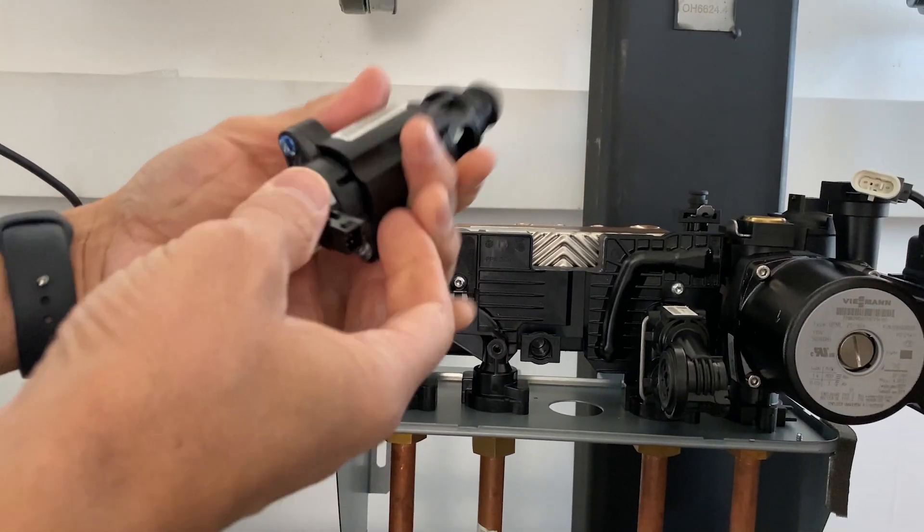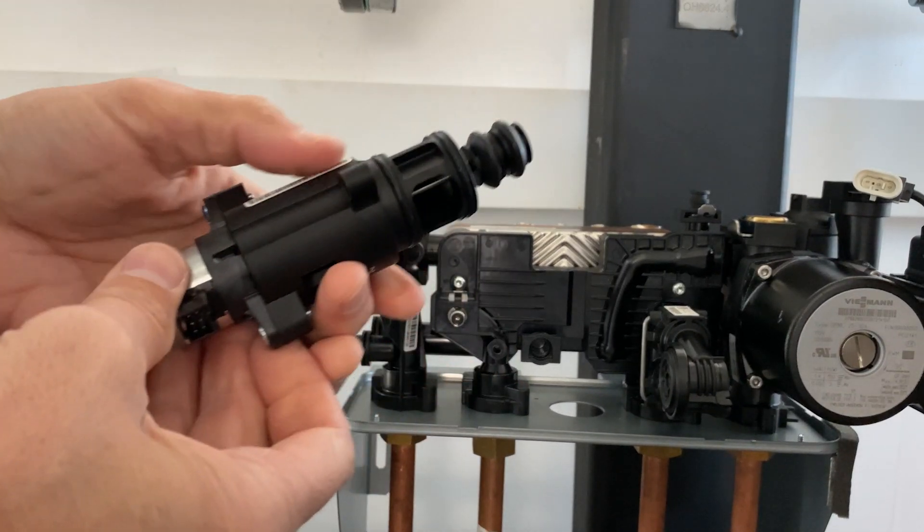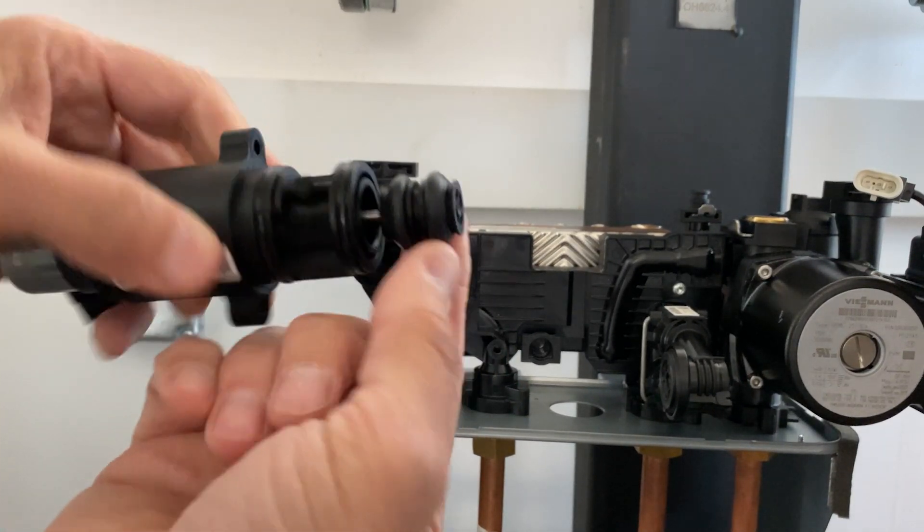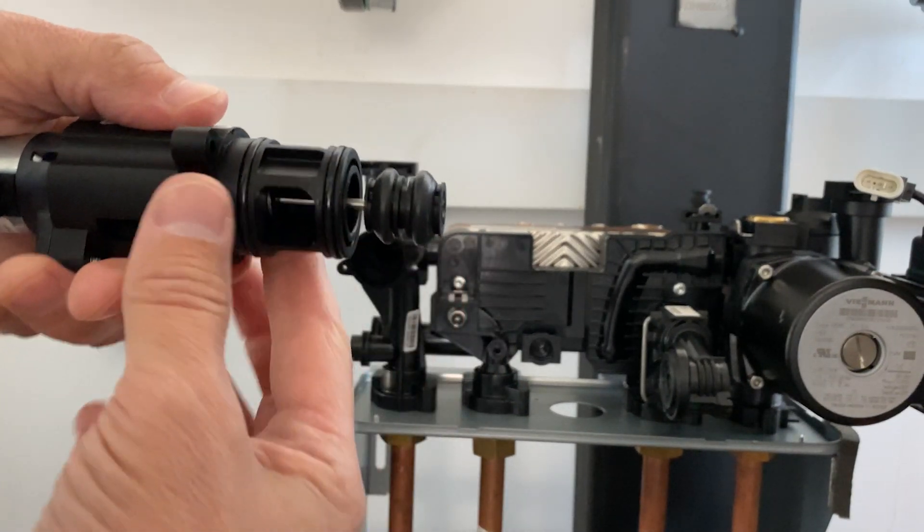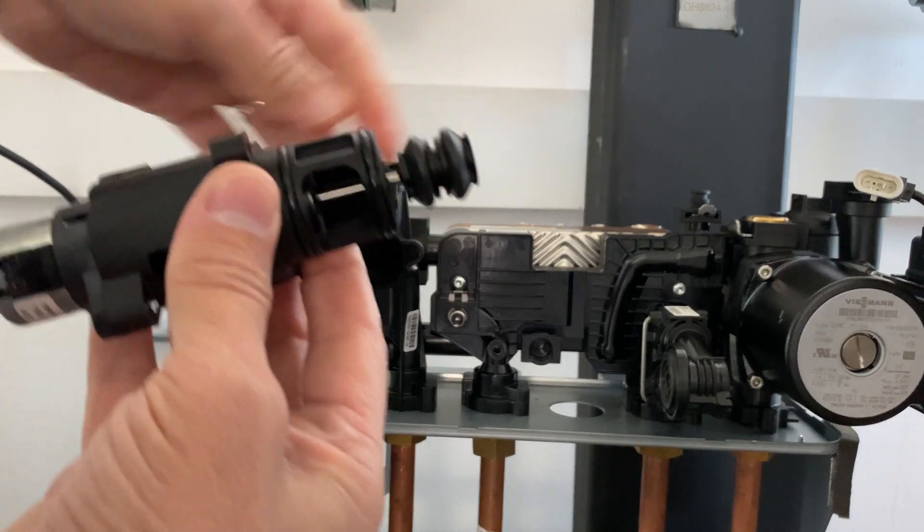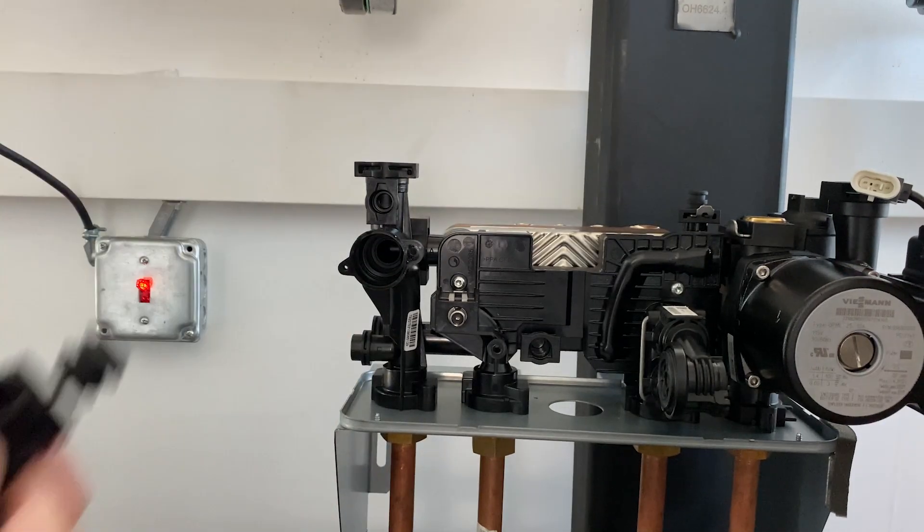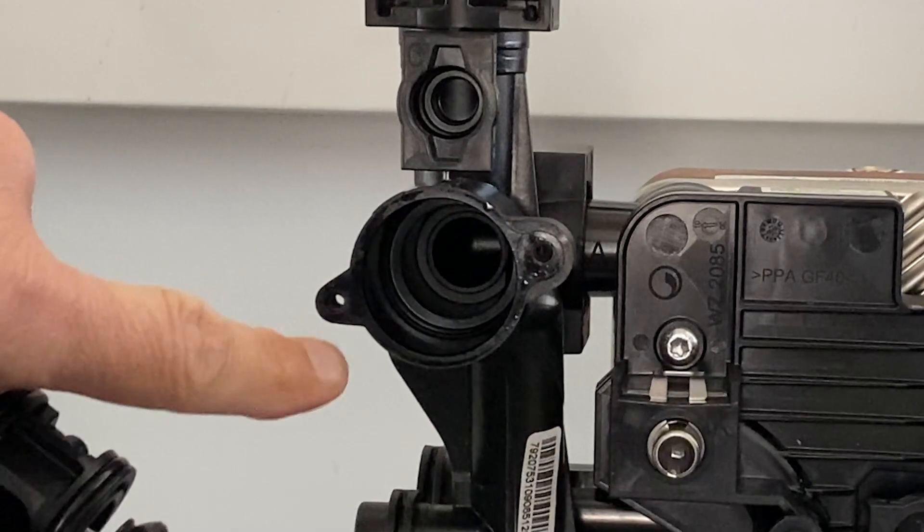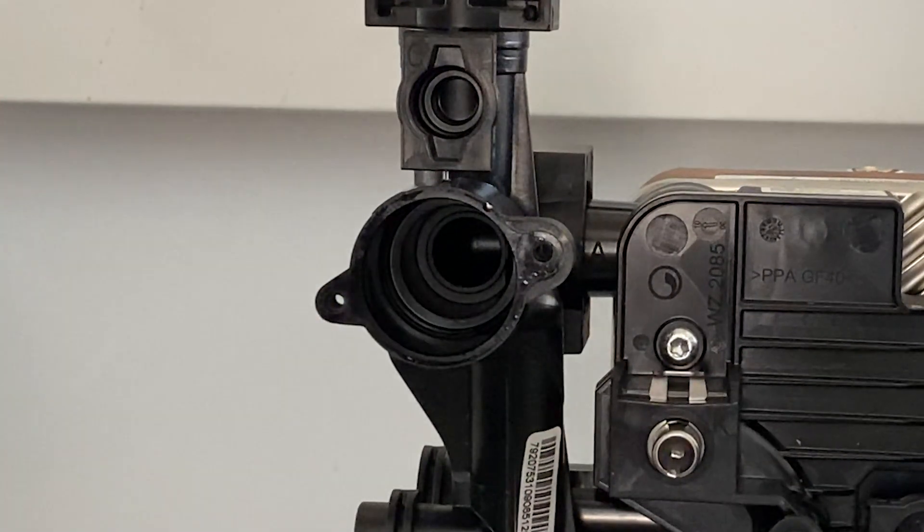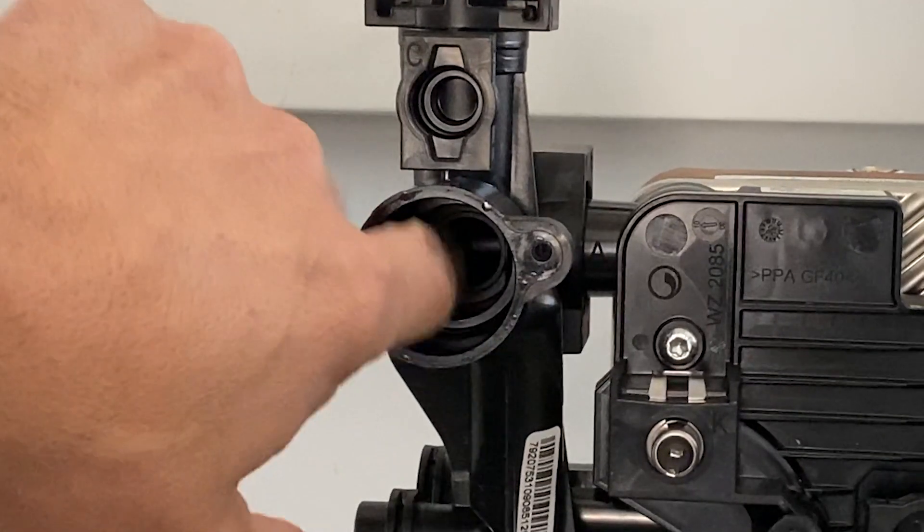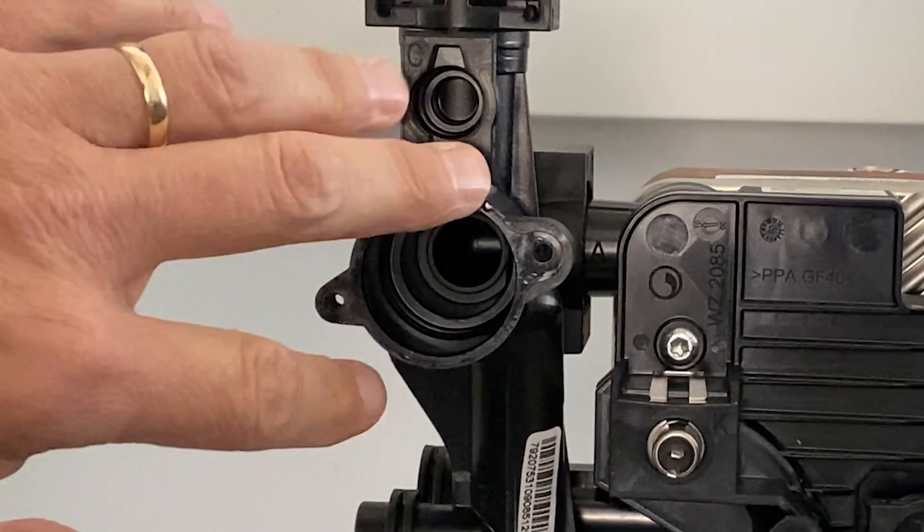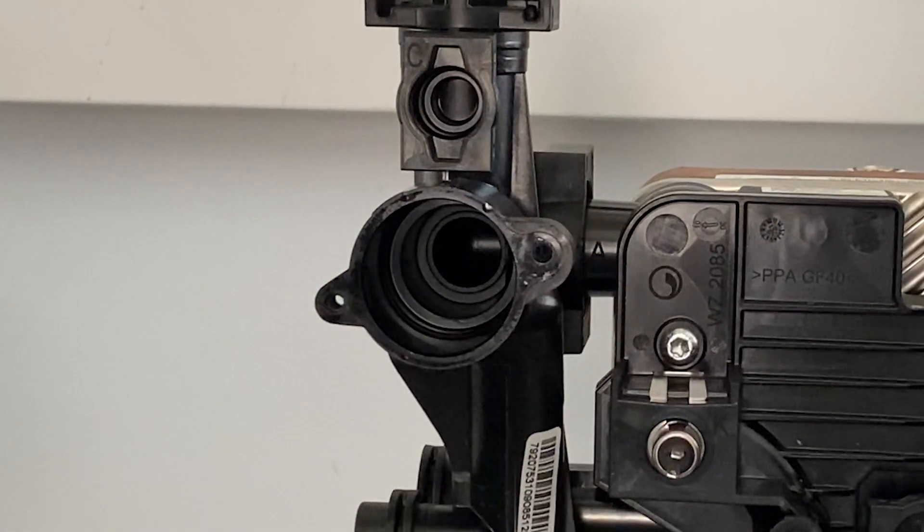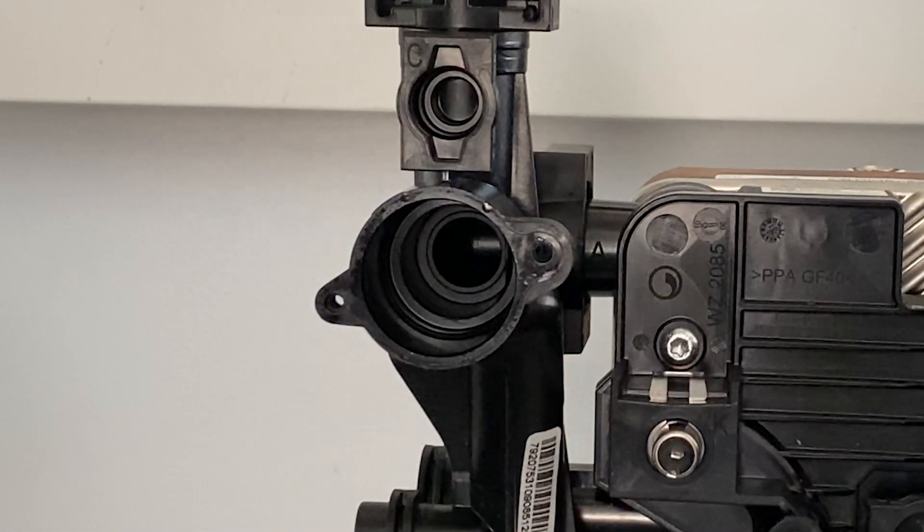And removing the motor assembly we can see we have our seals here. In this case we can inspect and clean those. We can also now inspect and clean the actual valve body, make sure that we have no significant fouling or debris in there.